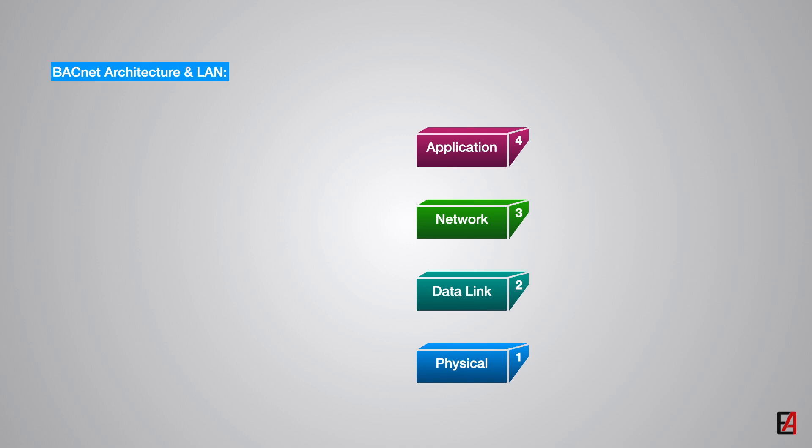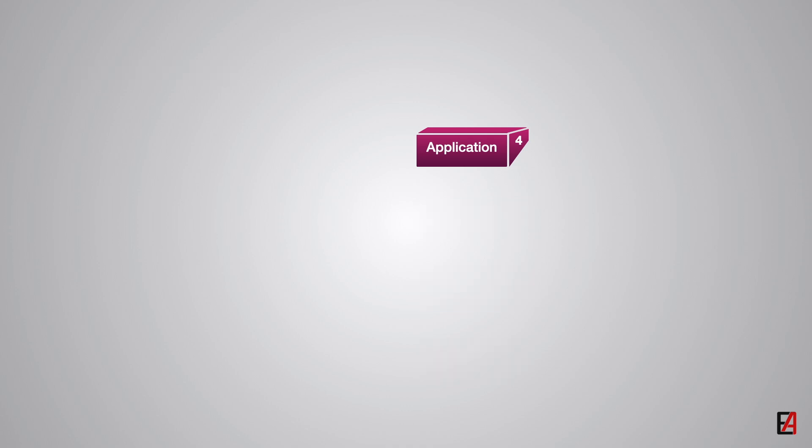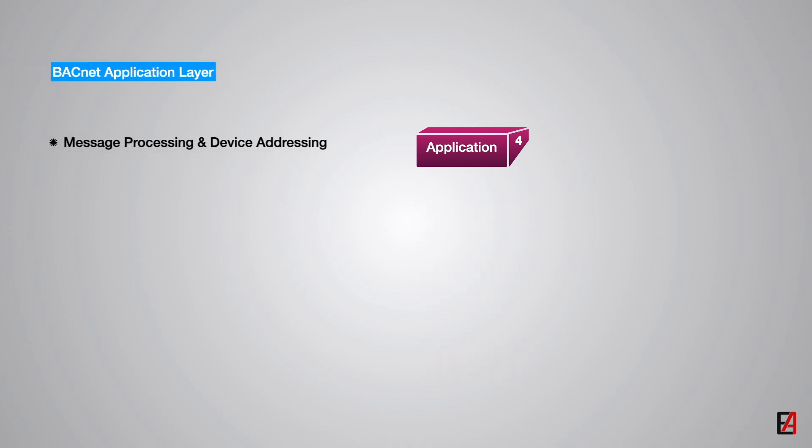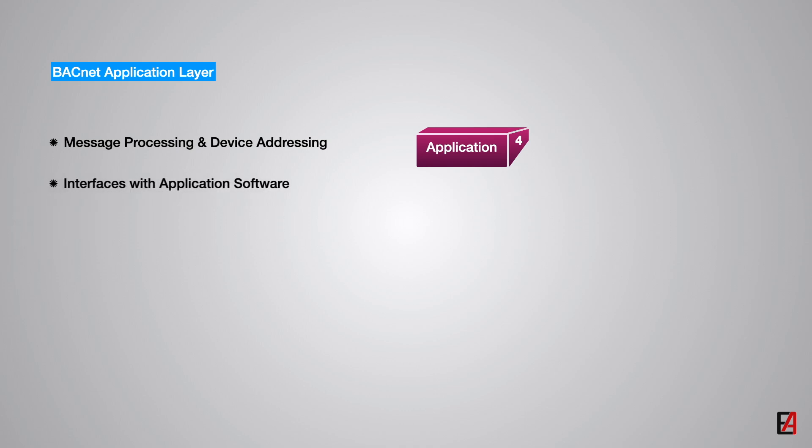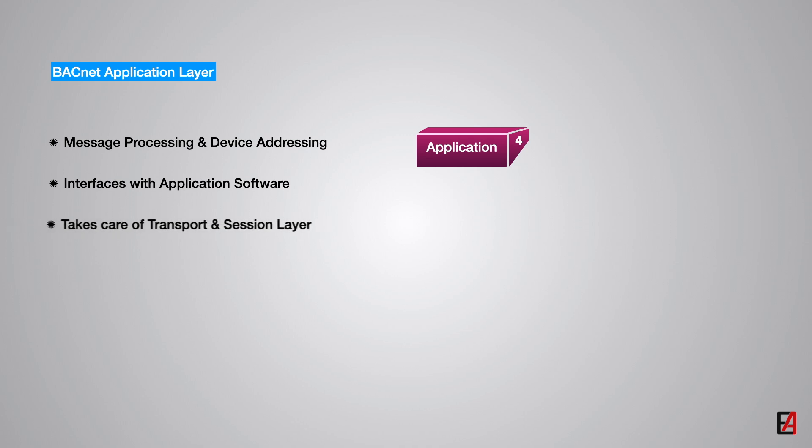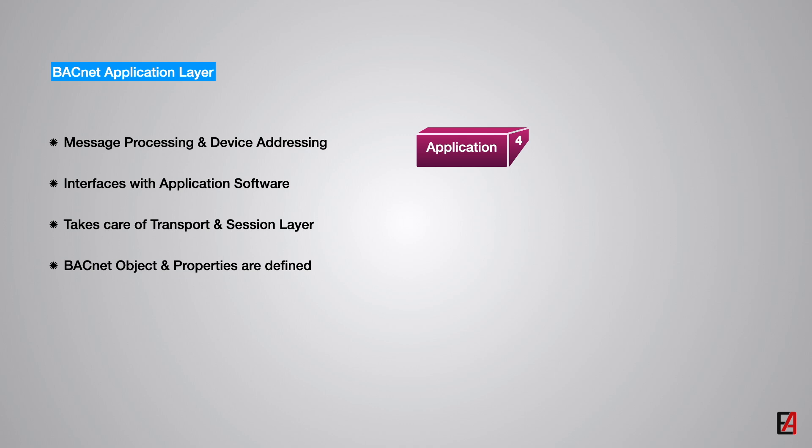The four layers from the OSI model within the BACnet architecture are application layer, network layer, data link layer and physical layer. All message processing is handled at the application layer including device addressing. The application layer decides what to do with the BACnet message. This layer handles the actual interface with the user application program. It also takes care of mechanisms associated with transport and session layers. This is where the BACnet objects and properties are defined.